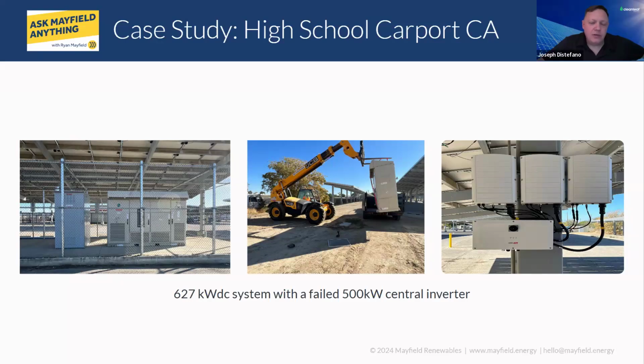Then outside the electrical side, there was all the California seismic mounting and related inspections. All in all it was a lengthy project from pre-construction to permitting to build, but I'd say we're up to about 13 repowers with Cleanleaf in the last 3 years. It's probably the one we're most proud of because we caused zero impact to the school. We didn't saw cut their parking lot, and we didn't have to go back to the client and say we thought that was a 2 inch conduit but it's actually 1.25 inches, since we did a thorough survey upfront. It was definitely a successful project. We energized it about 9 months ago, and I haven't gotten a call back. I talk to the client weekly on other projects, and he's super psyched about the outcome. It was a good project for sure.